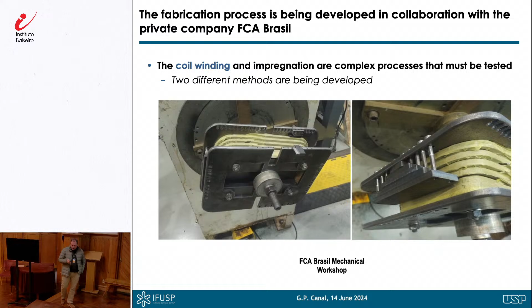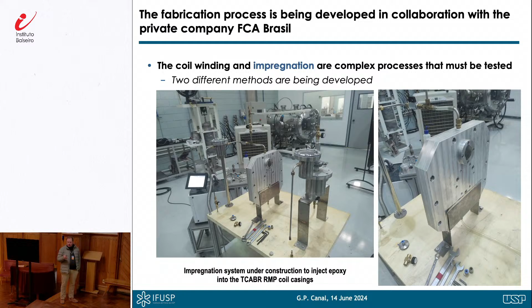Basically we have the coils inside and some space here for the epoxy. It flows down here, then goes up, fills this region, and then goes to another reservoir. We have to do this a few times to remove the bubbles, and we have to apply negative pressure with respect to atmospheric pressure to make this liquid epoxy move. Then at the end, hopefully, we have the conductors in their position with the electrical insulator correctly positioned.